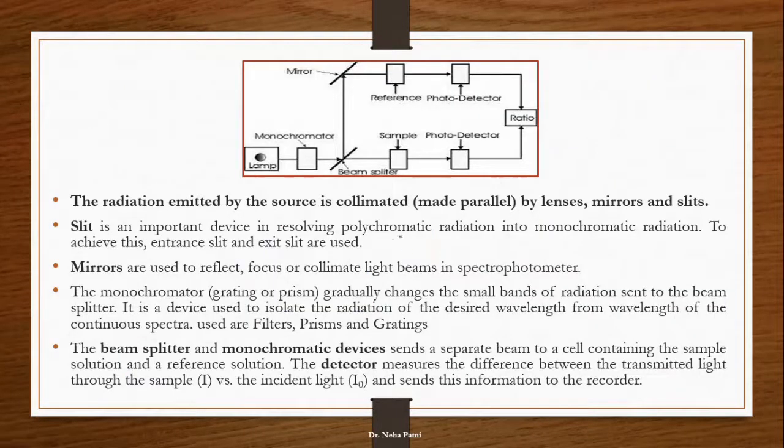Now coming to the double beam - double beam has some extra components. It is double beam so you have to use a beam splitter. The beam splitter and monochromatic device basically send the separate beam to the cells. You have two cells now so you have to split the beam into two. A beam splitter is extra, then there is a mirror, which is also extra because it is going to diverge the light to the respective areas.